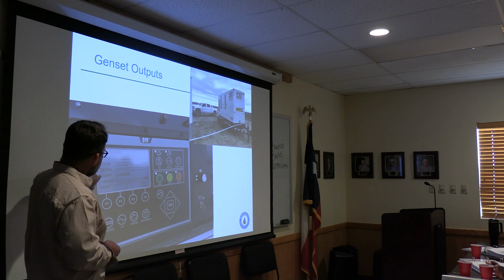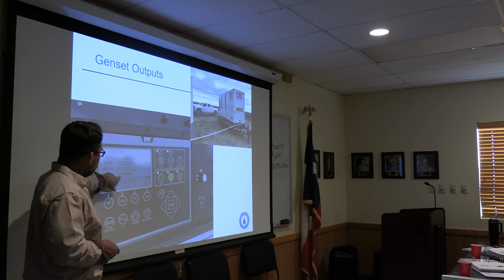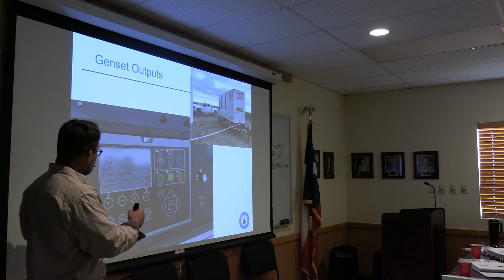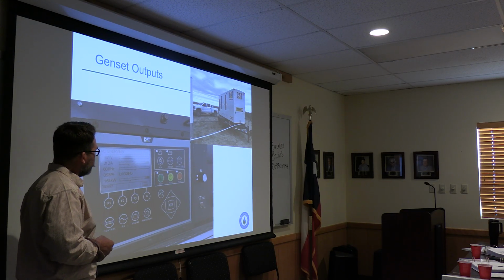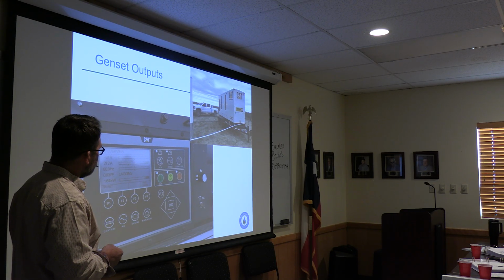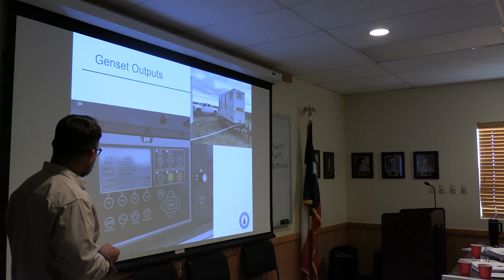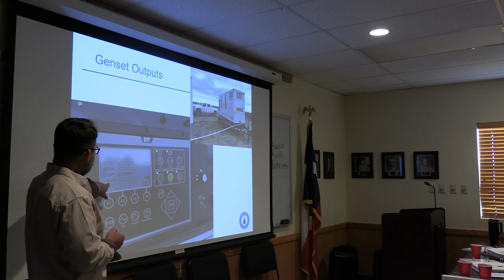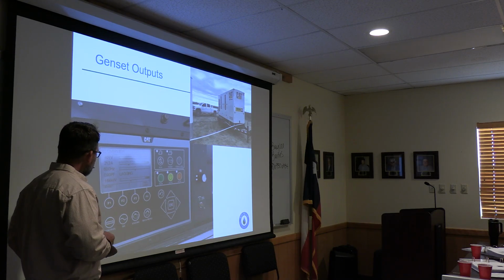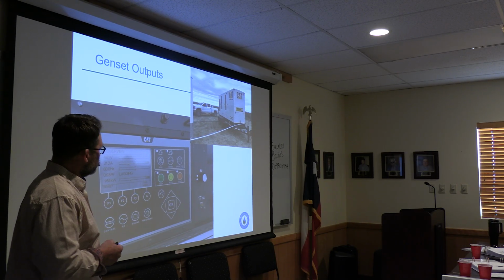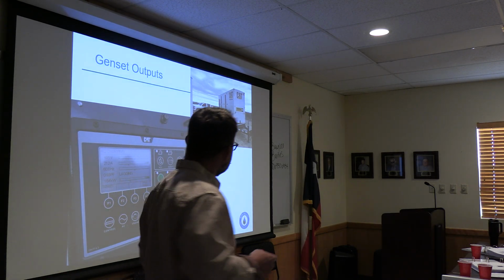The power factor is 0.93 lagging, which is directional. Most all of what we're going to look at is going to be a lagging voltage rather than a leading voltage. And that's where we get those predictable power factors from. And then you add this all up, and the actual power is 164 kilowatts. So a little bit over 200 horse here.